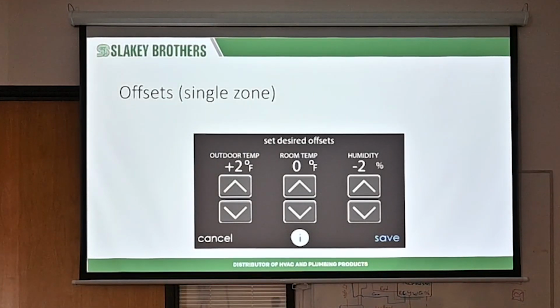Offsets. If your controller or your zone sensor or your little smart sensor is off by more than a couple degrees, you're going to have to replace it. It's going to get worse. Okay? But if you're uncalibrated by the slightest amount, 1 degree, 2 degrees, you can go to the room sensor, or you can go to here, the desired offset, and adjust it a little bit to correct that if it's a little bit off.